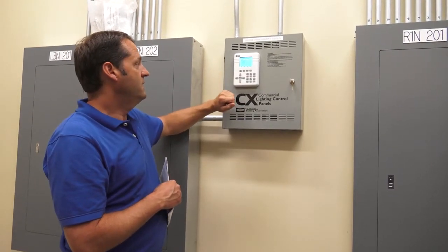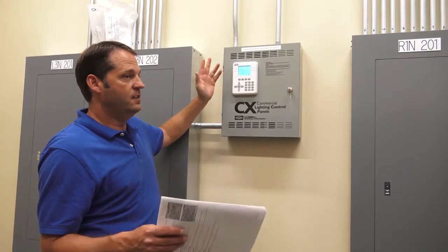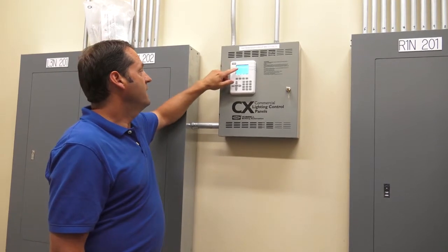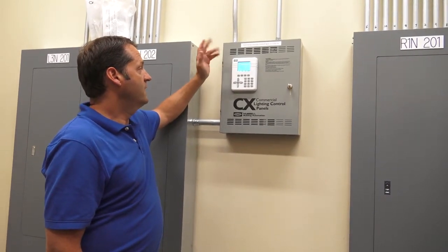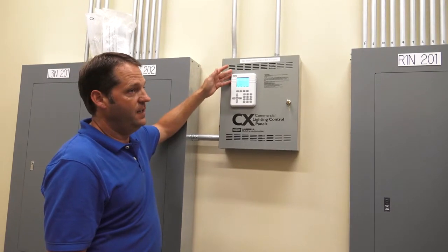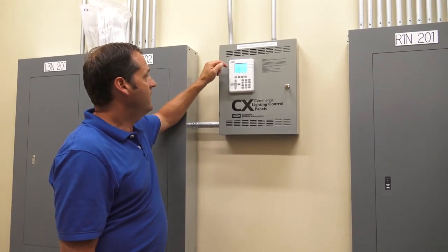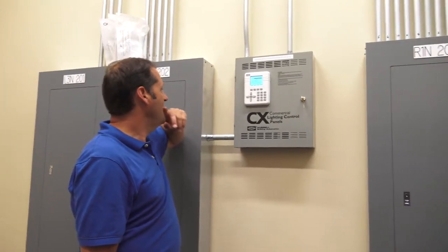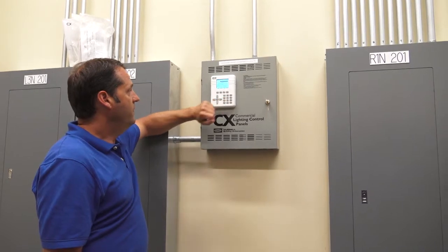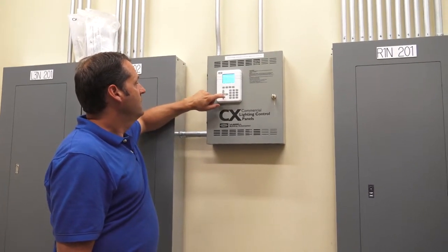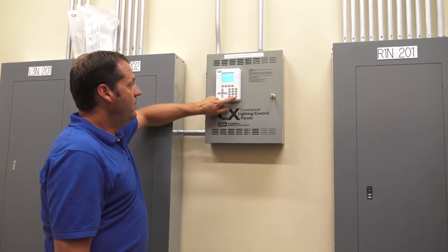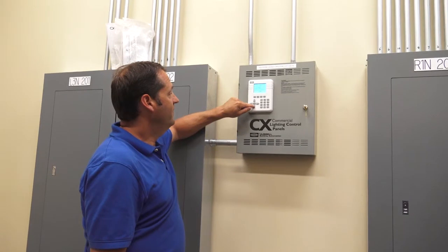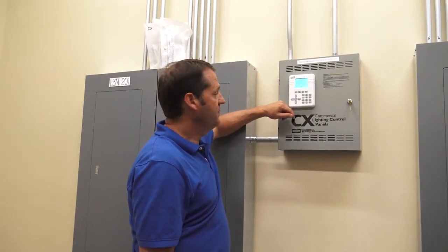Schedules, that's exactly like we talked about, it's setting a schedule by time. On at this time, off at that time. We've got schedule number 1, which is 6 to 8, which is on at 6 a.m., off at 8 a.m. Schedule number 2 is inside off, which I think is that sweep we talked about. Again, if you wanted to set up another schedule, you just go in here, create the name, come down here, say which relay or groups you want to control. We'll talk about priority here in a little bit, and then save it.